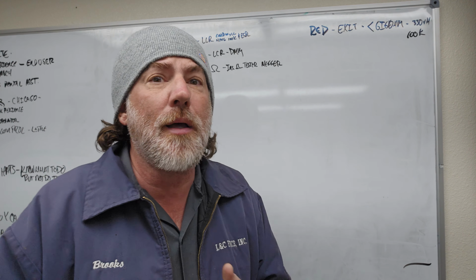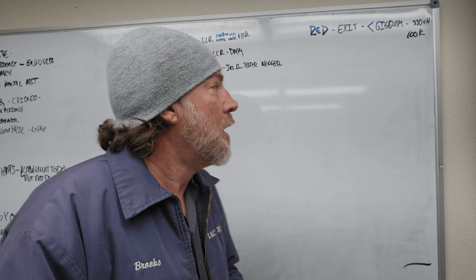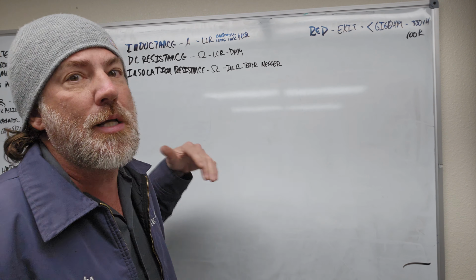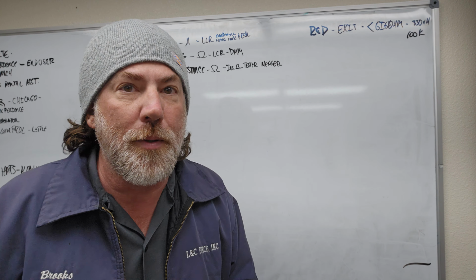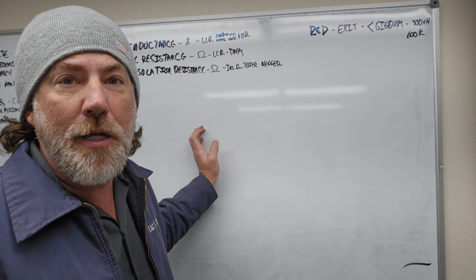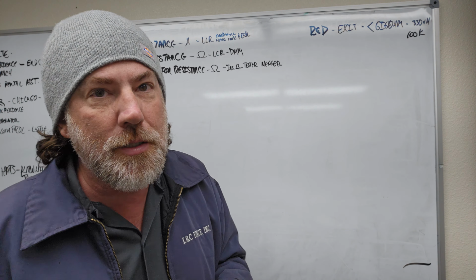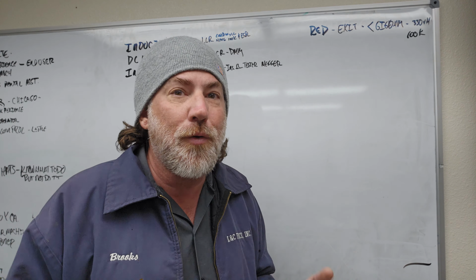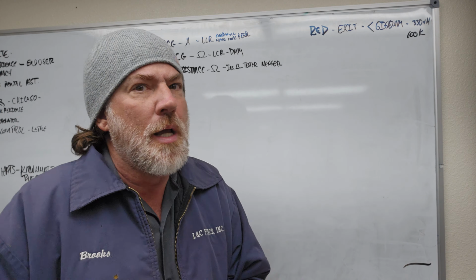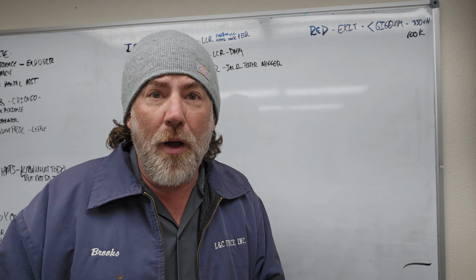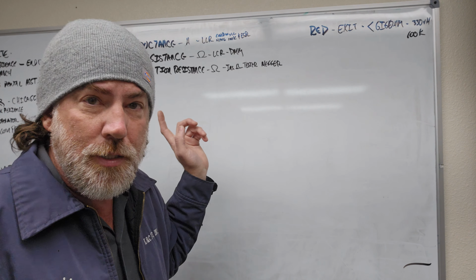Now, some loop detectors will tell you if it can tune the detector to that loop or vice versa, depending upon how it is. So the point that I want to make in this is these are all things that you need to document to actually be able to get a true representation of what the loop is doing and why high potential, high pot, or megging a loop is not the go-to to test it. Not saying don't test it, I'm just saying if you're telling somebody to test it and walk away without understanding what the DC resistance is, then we have a fundamental misunderstanding of how analog circuits work and what that device is actually telling you. Inductance is one, DC resistance is the other.